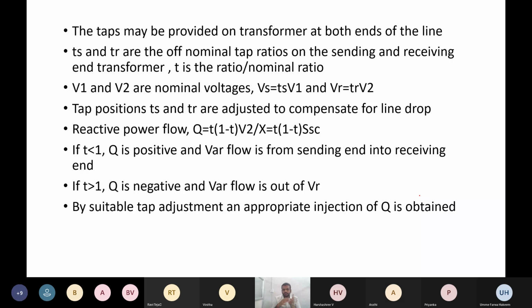And the reactive power flow. So the total reactive power flow in the circuit will be given by Q is equal to T of 1 minus T into V2 by X. So what is T? T is our ratio of nominal ratios. T is the nominal ratio. Okay, so Q is equal to T of 1 minus T into V square by X. Not V2, V square by X.